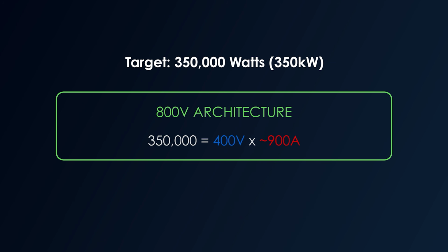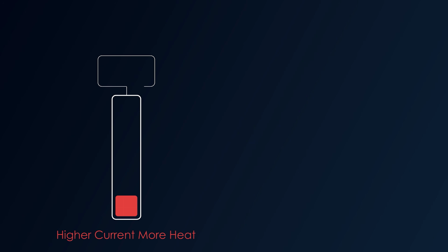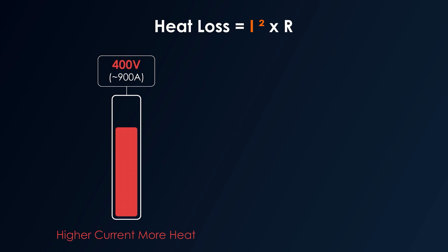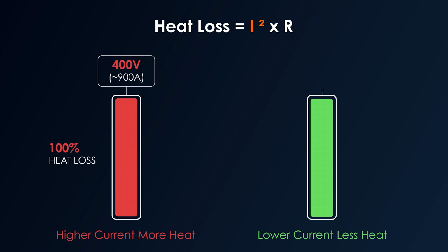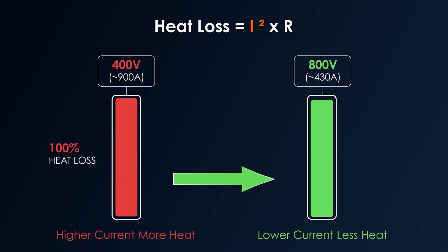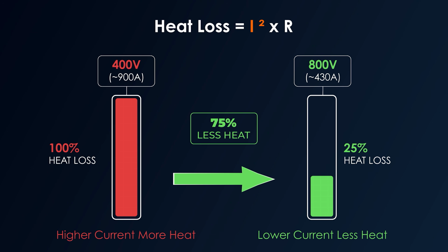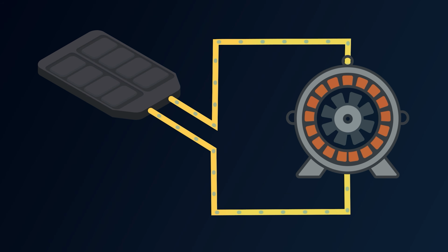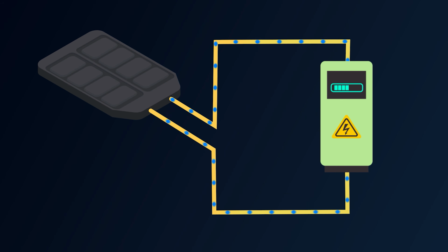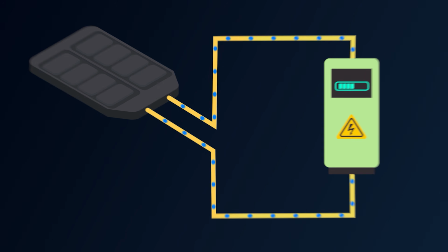But if we double that voltage to 800 volts, the math changes. To get the same 350 kilowatts, we only need half the current, around 430 amperes. Because heat generation is tied to the square of the current, cutting the current in half reduces our heat losses by a massive 75%. So 800 volts lets us use thinner, lighter cables and charge much faster.